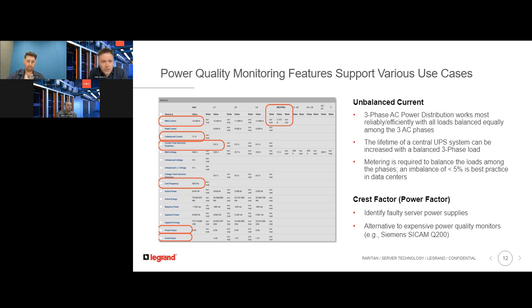So AC current sine wave distortion usually comes from switched mode power supplies which are not working normally anymore. Inside these power supplies, you can find big capacitors for the energy storage. When these capacitors are getting older or getting exposed to hot ambient air for too long a time period, they lose their storage capacity over time, which leads to an aging effect and eventually to a power supply failure. So in other words, this crest factor is a good indicator for IT loads with faulty power supplies, and you should then schedule a replacement service soon.